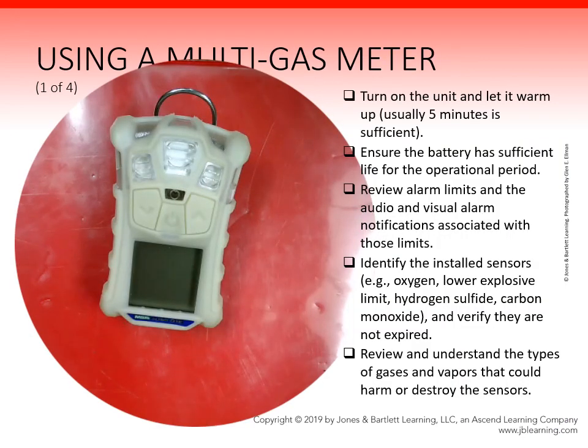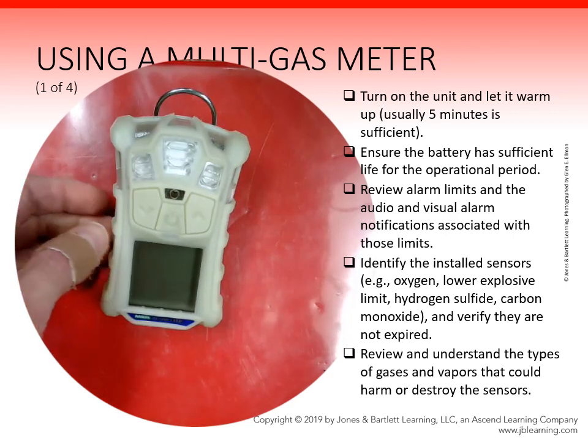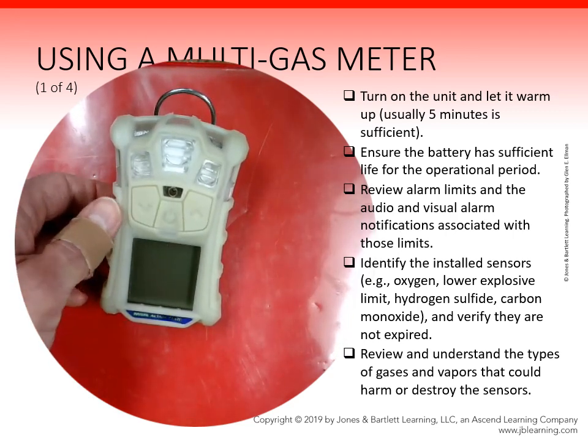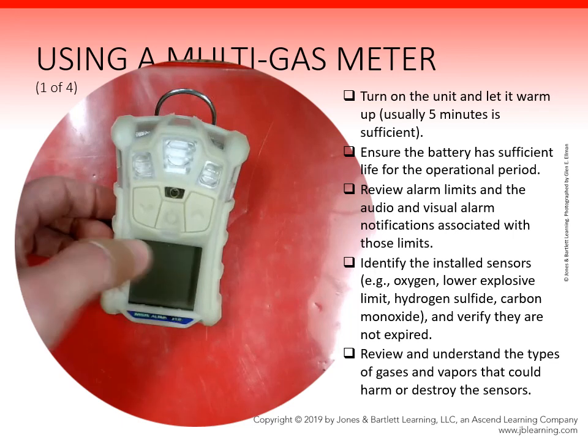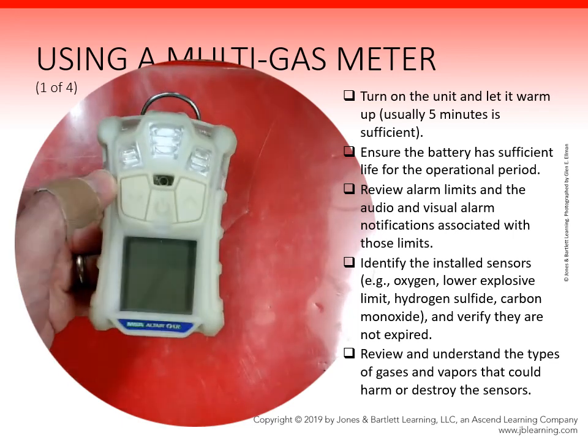So moving on, we're going to go ahead and power our meter up. We're going to watch it go through its self-test, and then we're going to do a fresh air setup. During that power on self-test, it's going to give us a lot of information that shows us the meter is ready for use. So what I'm going to do first is I'm going to turn that button on, and as soon as I do this, you're going to see all display segments in that screen activated.